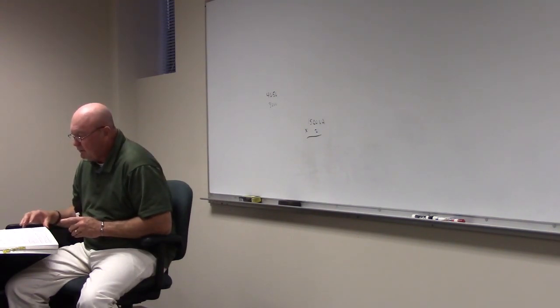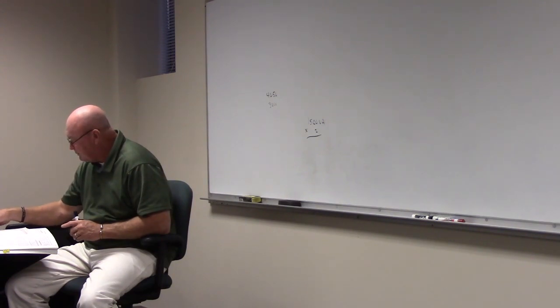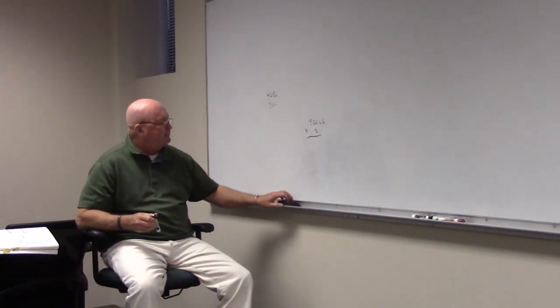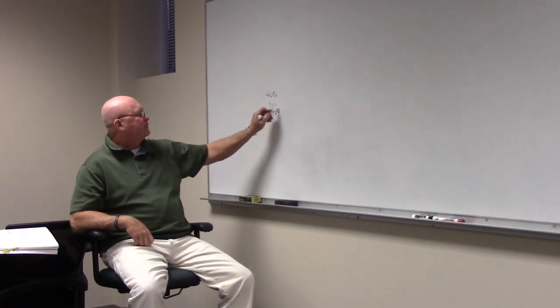The next step says there has to be a laundry circuit. 210.11(C)(2), we go back to there. It says there has to be a laundry circuit. Let's go back to 210. C2, in addition to the number of branch circuits required by other parts of the section, at least 1 additional 20 amp circuit shall be provided to supply the laundry receptacle. Is the laundry receptacle the dryer receptacle? No. Completely different. So we have to have a laundry circuit, and how many volt amps is it? It's 1,500, yeah. And again, because the NEC says that's the minimum requirement for that, it's 1,500.